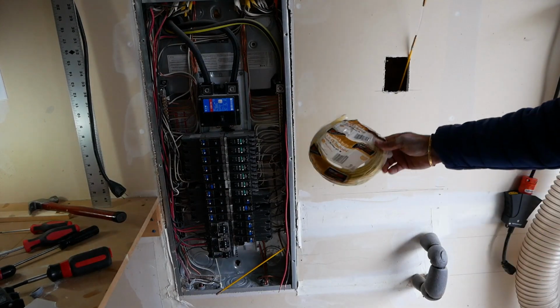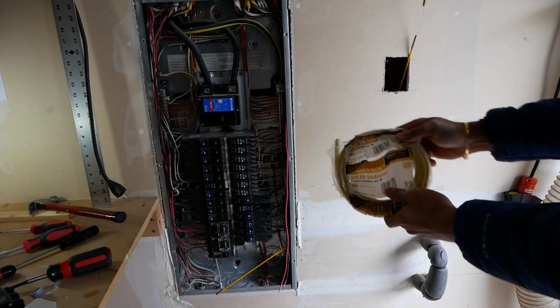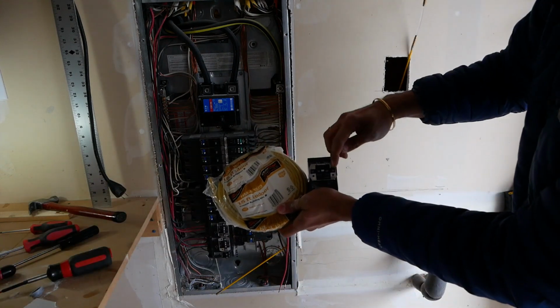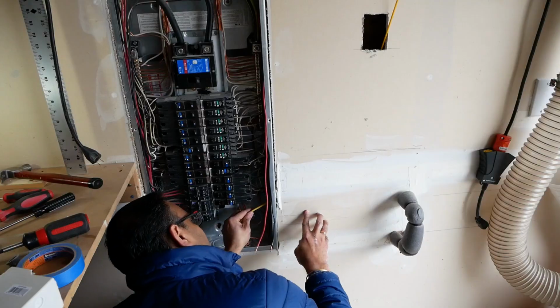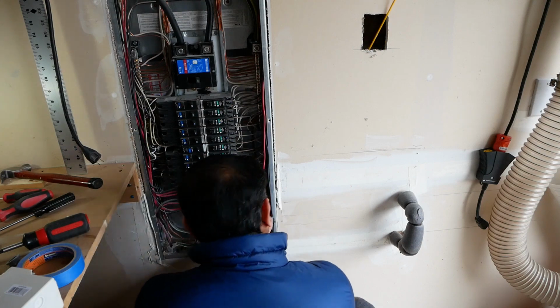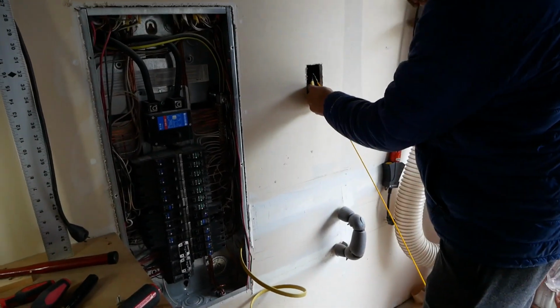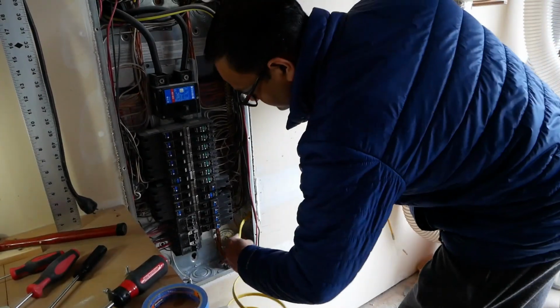As we are running a 20 amp circuit, we have to use 12 gauge wires. In this case, we ran 12-3, meaning there are 3 conductors in addition to the ground. The reason we used 3 conductors is because, in addition to 240 volts, we also want to run a 120 volt outlet on this circuit in the future.